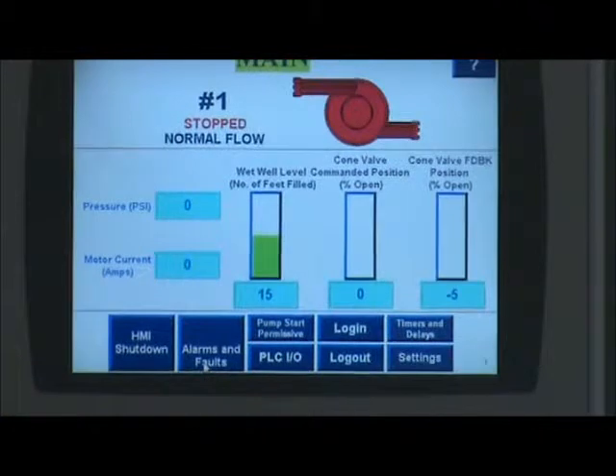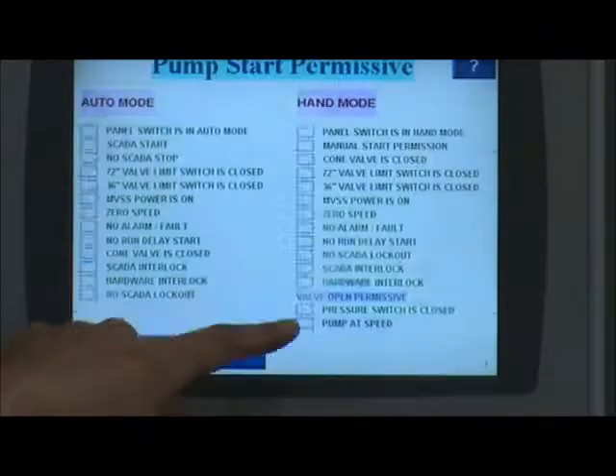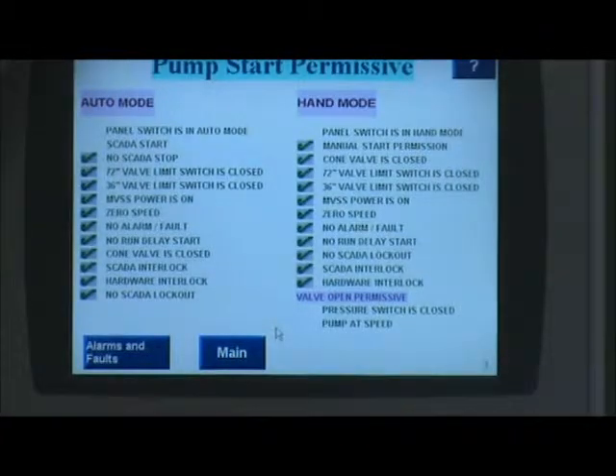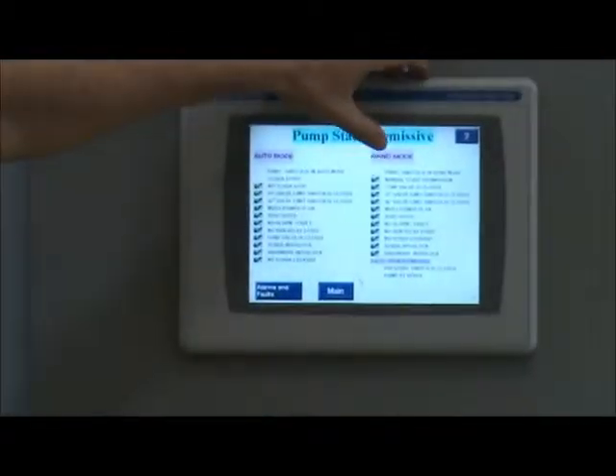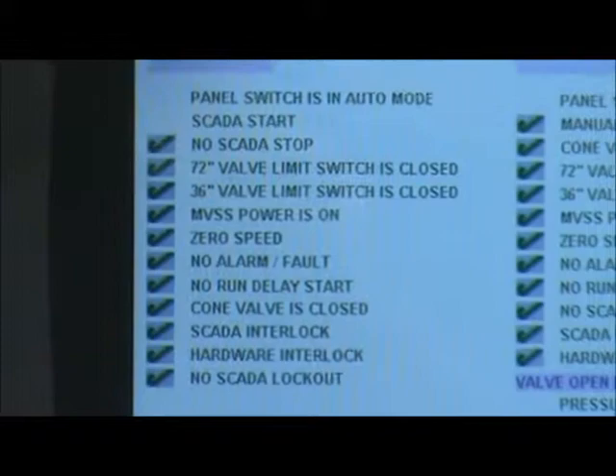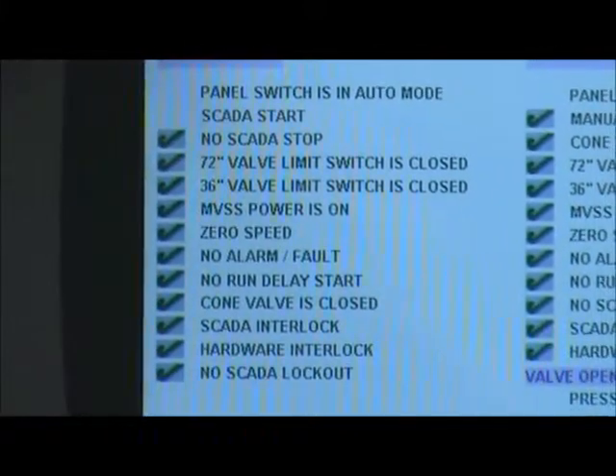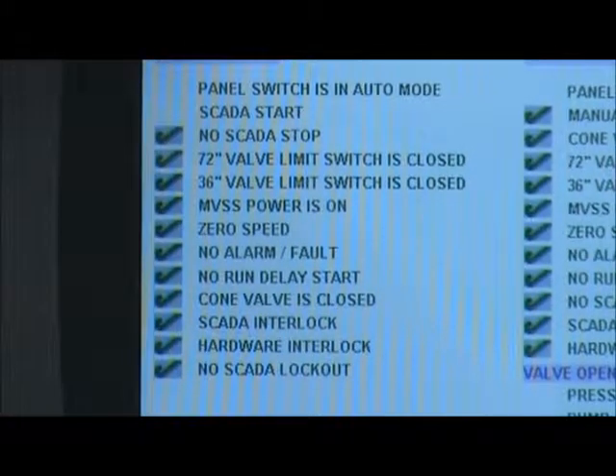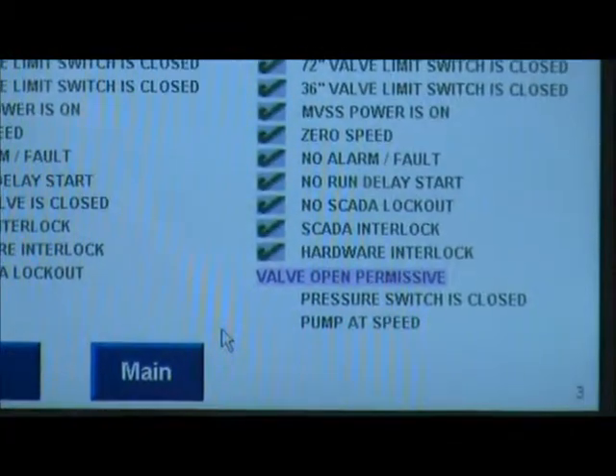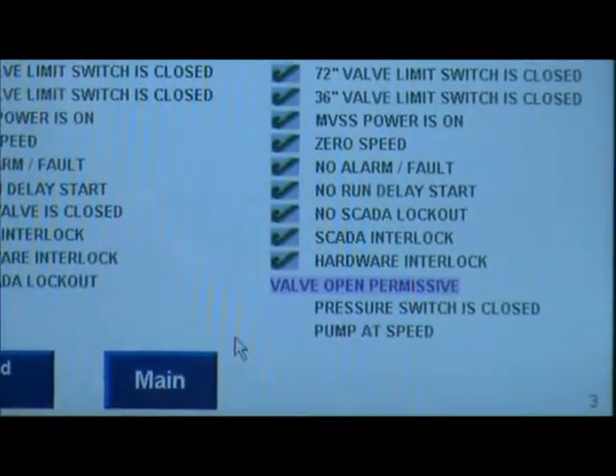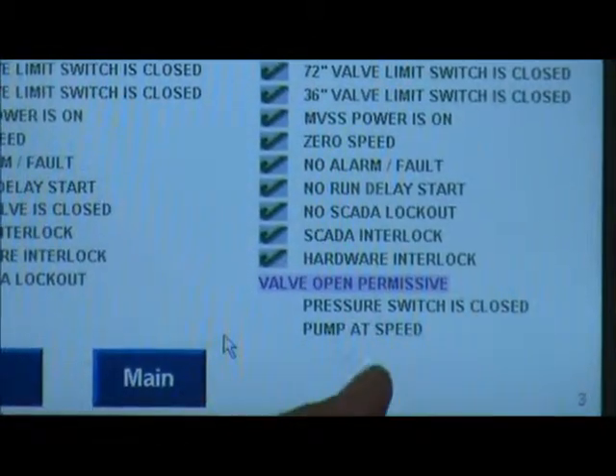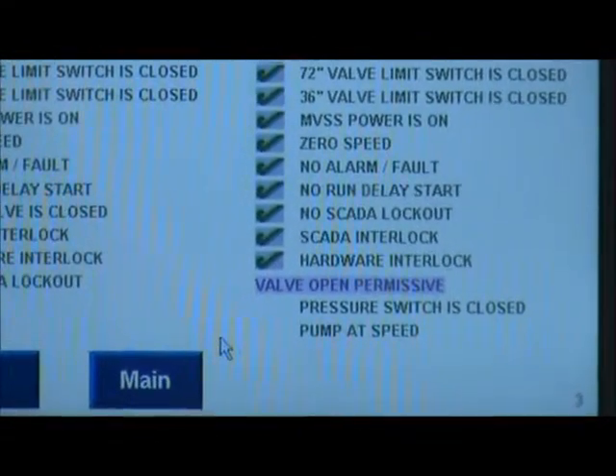The next navigation key is the pump start permissives. This screen shows everything that you need to run the pump, whether you're in auto or in hand. You need a check mark by each line to let the pump start. Then also, there are 2 permissives for the valve opening sequence. The pressure switch has to be activated, and then the pump also has to be at speed.